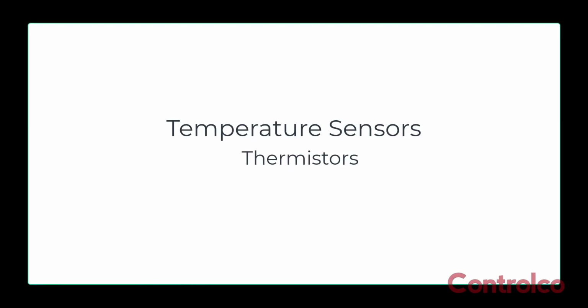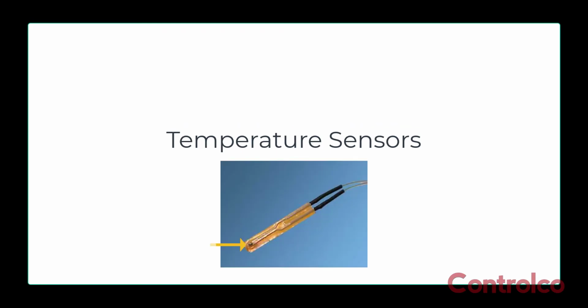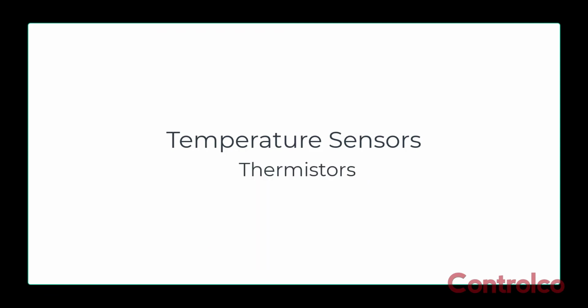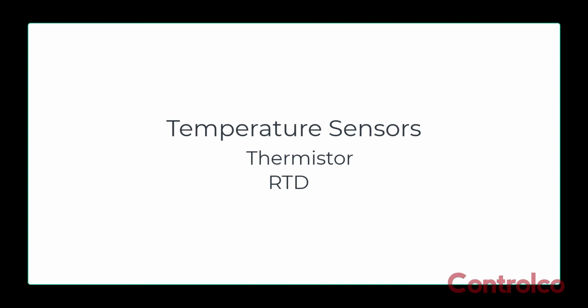So I've talked about thermistors when you're doing temperature sensing, and they're basically you're measuring resistance. If you got down into the physical piece of the thermistor, it's not actually just a bare resistor, it's a semiconductor. There's another type of temperature sensor that you're going to run across. Same basic concept, it uses resistance, and these temperature sensors, whether it's a thermistor or the next one we're going to talk about, which is an RTD, you're able to just put a meter on the probes coming off of the sensor and get a specific ohm value that will correspond to the temperature in the room.